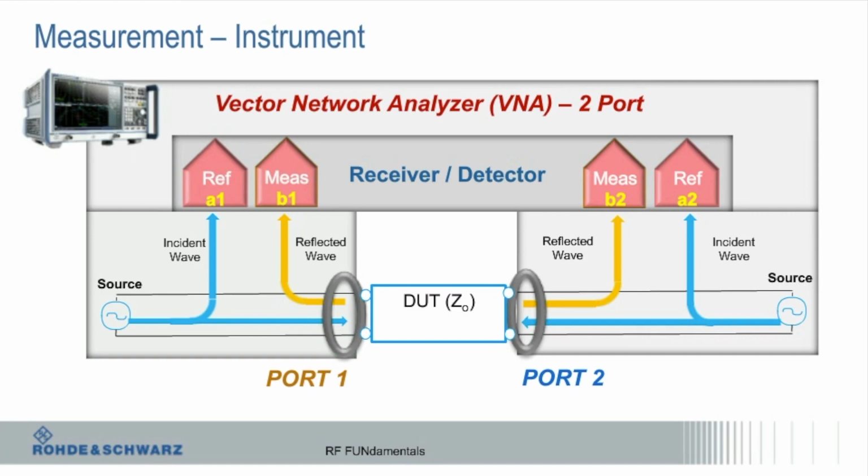So when I do a calibration, without getting into a lot of detail, I'm going to put known things right here and connect them between. When I connect one with a cable on, I know exactly what is supposed to happen, and it'll figure out what's going on between the front panel of the instrument and wherever you connected that standard.